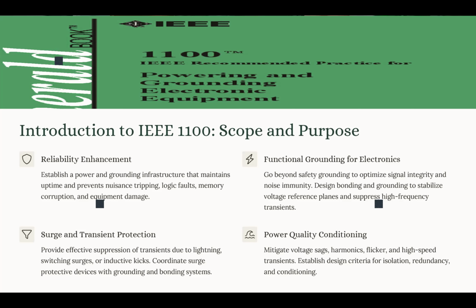Now, we also want to have a certain level of power quality conditions. So we make sure that we provide clean, stable, and regulated power for our sensitive equipment. Now, there are some issues that are typical, common, and happen a lot in power systems, like voltage sags, voltage swells, harmonics, flicker, and high-speed transients.